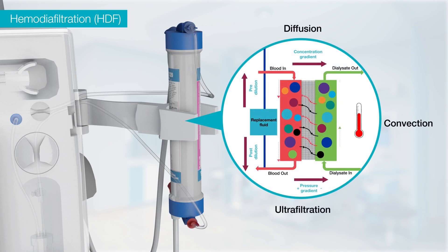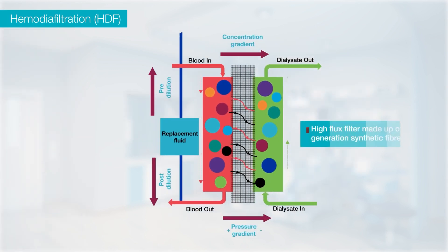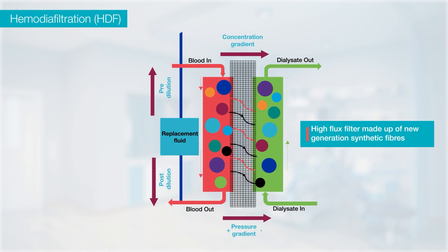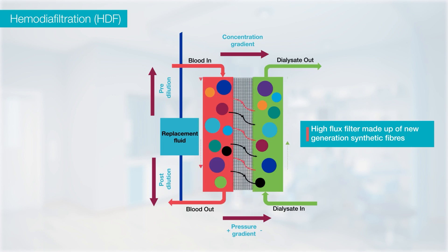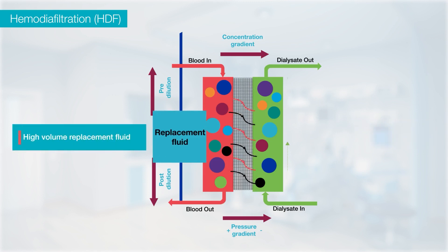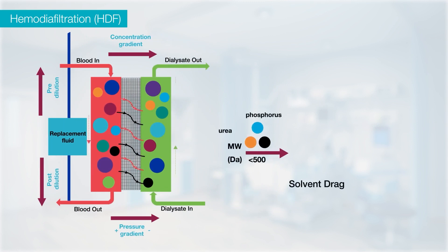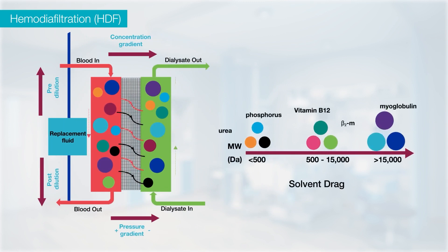During this process, the patient's blood flows through a high-flux filter comprised of new-generation synthetic fibers with a combined hydrophilic and hydrophobic structure, facilitating diffusion, convection and ultrafiltration. The convective forces are maintained through the hydrostatic pressure of high volumes of replacement fluid. HDF enhances the clearance of middle and large molecular weight uremic toxins along with small molecular weight toxins through a phenomenon of solvent drag.